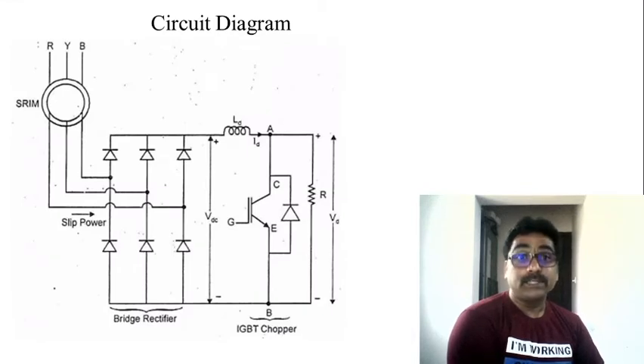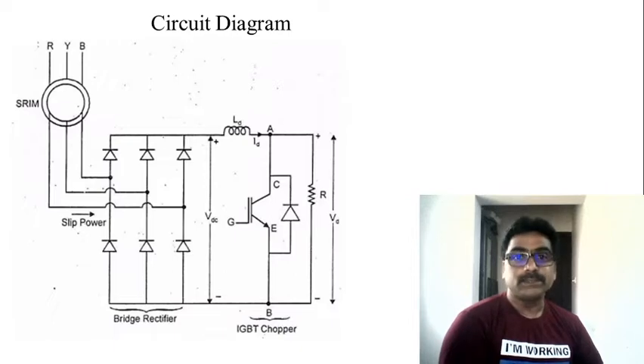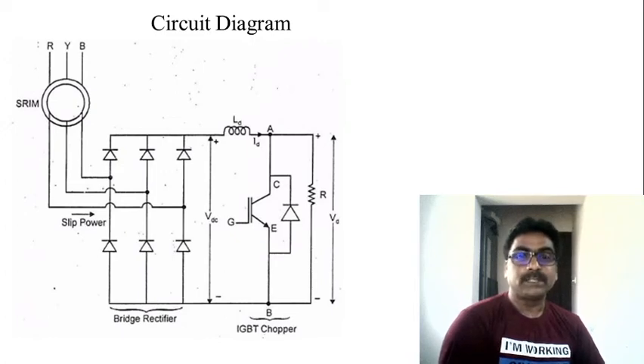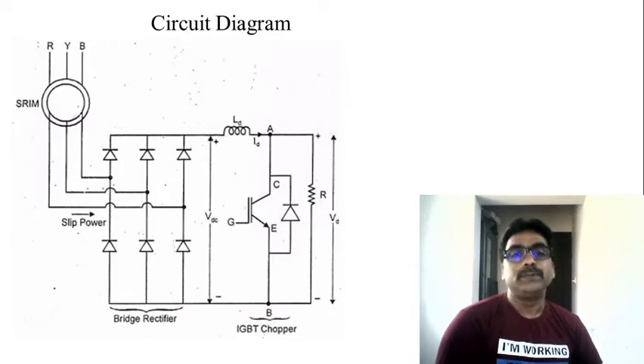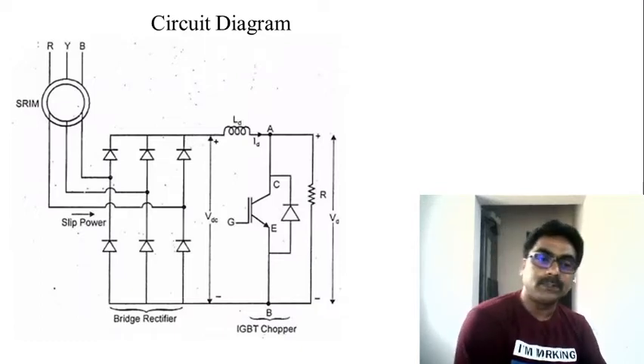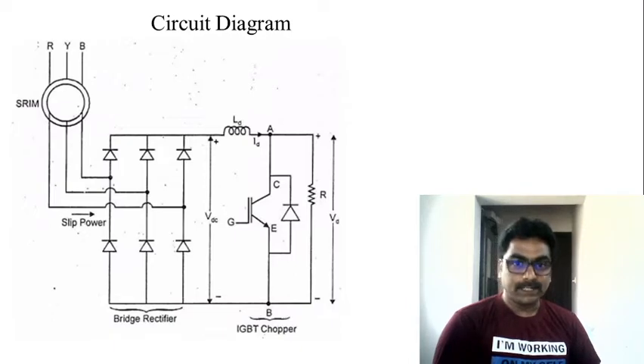I will go quite fast with the operation of the circuit and derivations to limit the time. This is the circuit diagram of the static rotor resistance control of induction motor drive. The stator is connected to the three-phase power supply, and the rotor side is taken out and connected to the resistor through two different power electronic circuits. The rotor side is directly connected to an uncontrolled rectifier — a three-phase diode rectifier — which converts the AC output into DC.